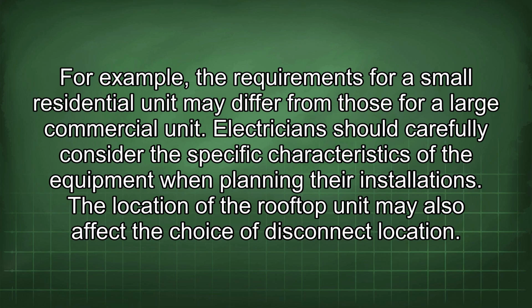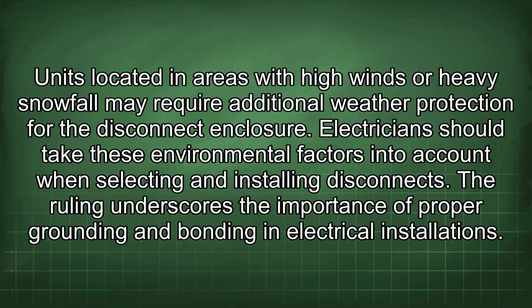The location of the rooftop unit may also affect the choice of disconnect location. Units located in areas with high winds or heavy snowfall may require additional weather protection for the disconnect enclosure. Electricians should take these environmental factors into account when selecting and installing disconnects.